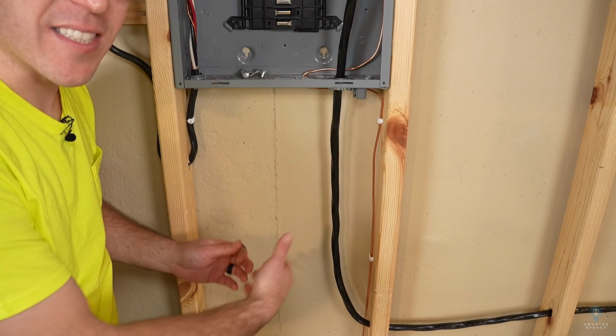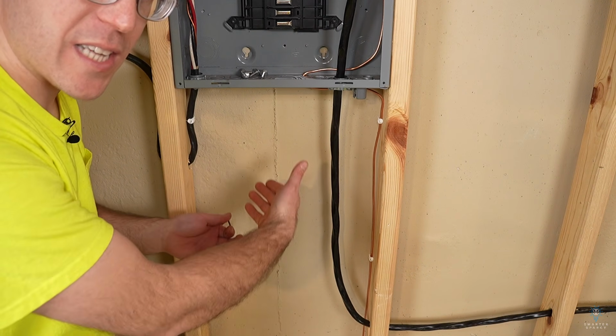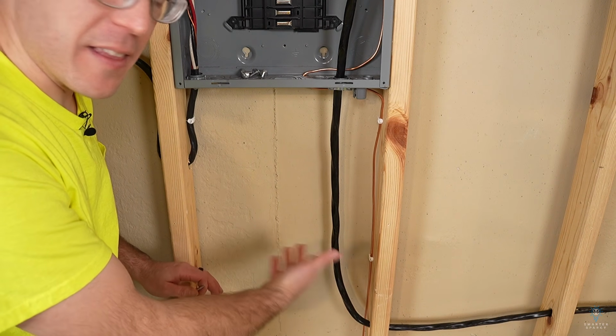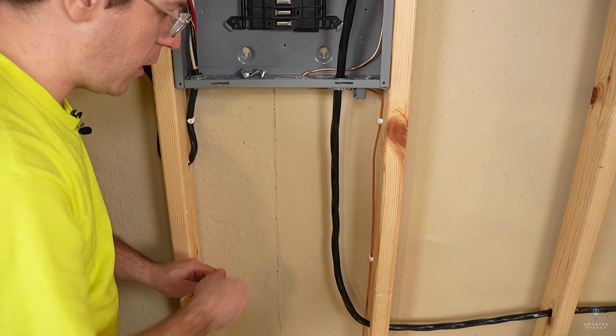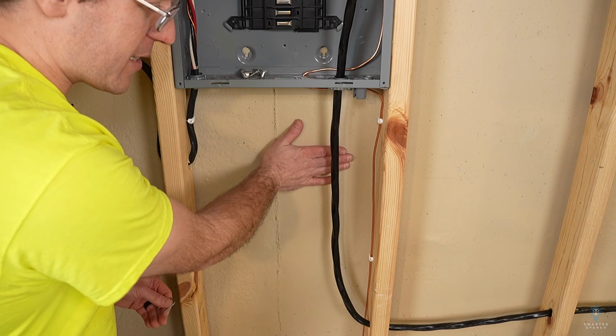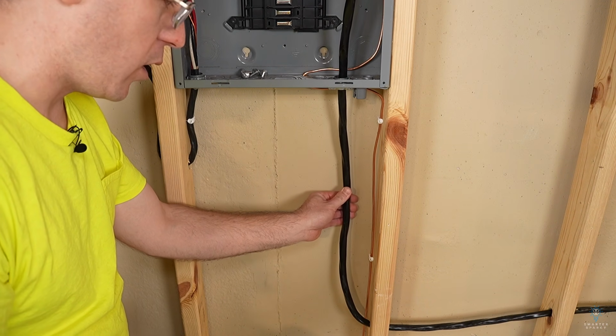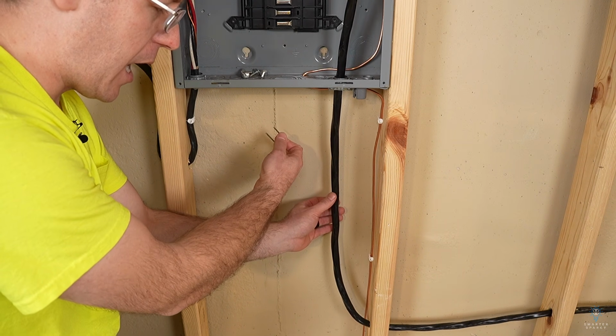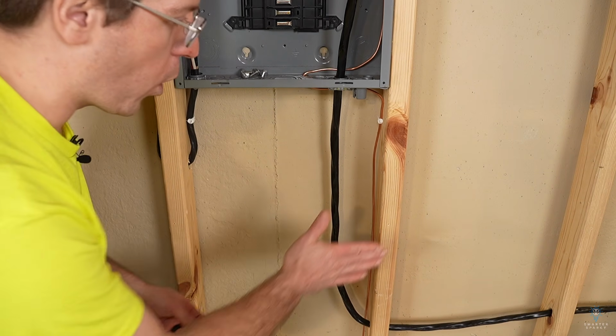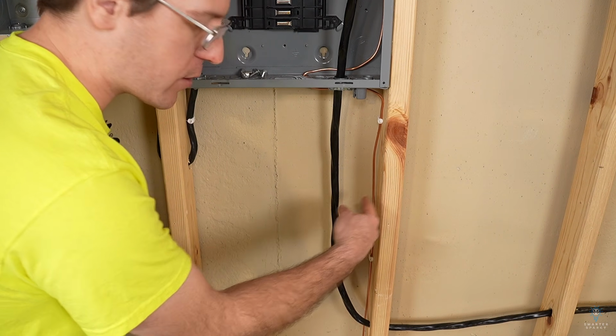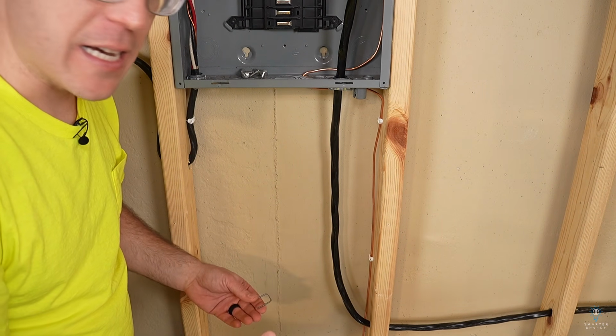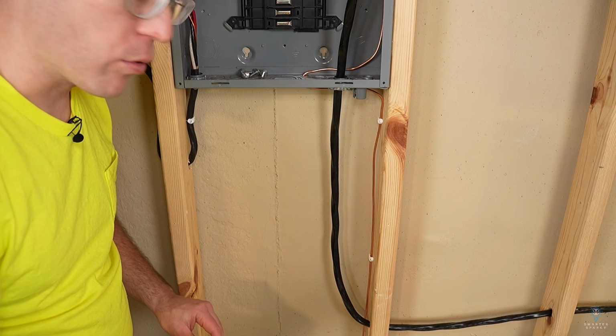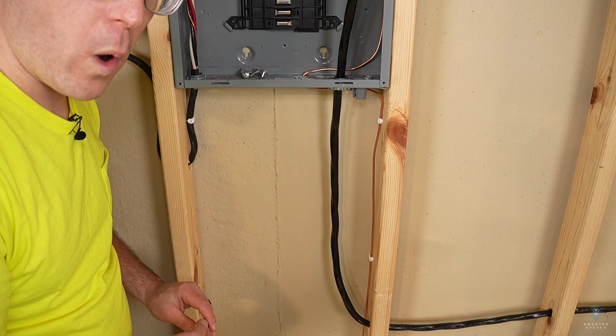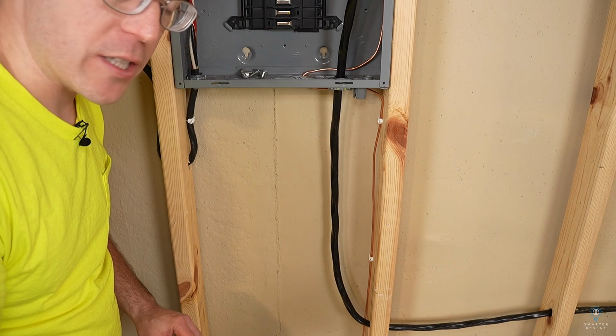So maybe this is the center of a house or something where both sides are accessible. If we were taking this in the literal sense, where there is a concrete wall behind there, then the back side doesn't matter. You could staple this as close to the back side as you want with that concrete there. It's just 1.25 inches from any face that sheetrock screws are going to get run into. The idea is if a sheetrock screw gets put in crooked, we don't want it going into our wire. That's why there's a 1.25 inch clearance rule.